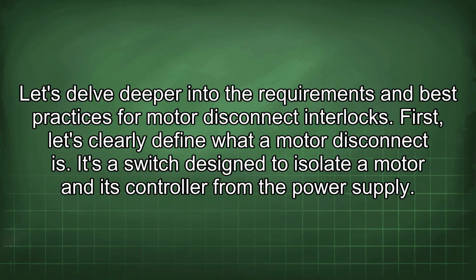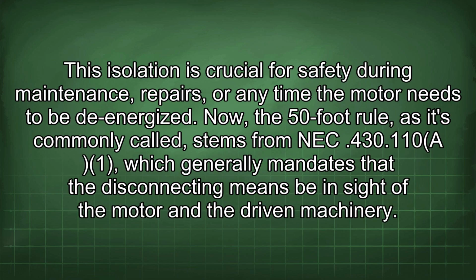First, let's clearly define what a motor disconnect is. It's a switch designed to isolate a motor and its controller from the power supply. This isolation is crucial for safety during maintenance, repairs, or any time the motor needs to be de-energized.